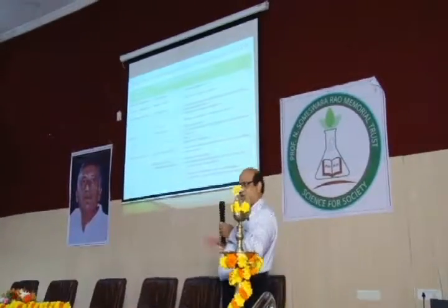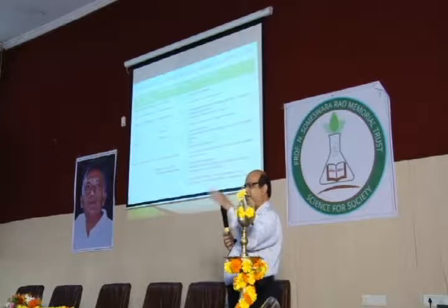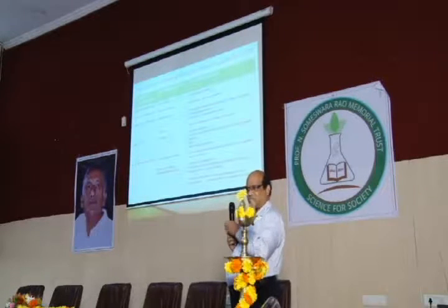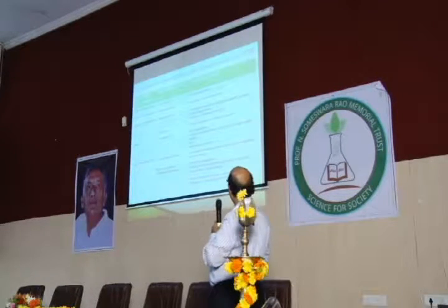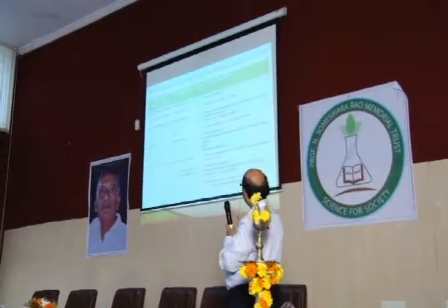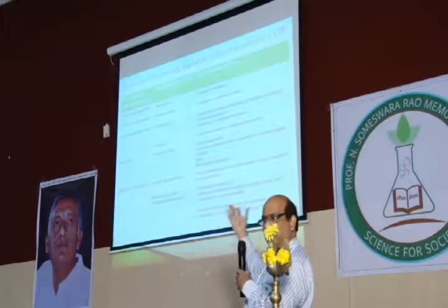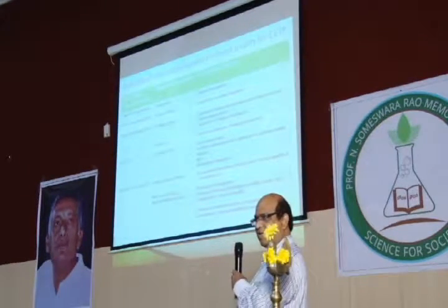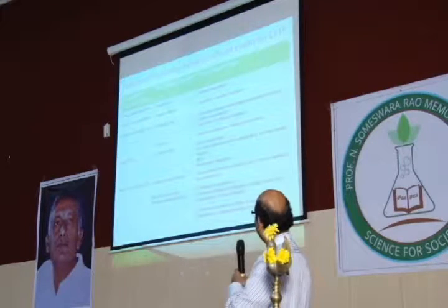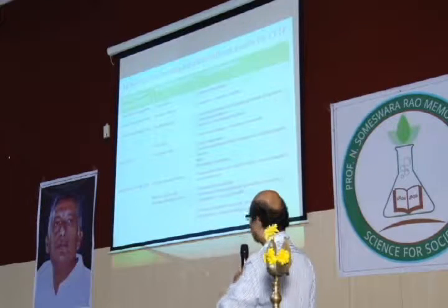What do you have to do? What is the technology for low TDS and low COD effluents, which are not having anything? What should we do? If it is low TDS and low BOD, then simply any chemical treatment we can do. Otherwise, if it is low TDS but high BOD, then go for any anaerobic treatment, whether UASB or anything, followed by biological. If it is low TDS and of course high COD, chemical oxidation is also suggested.